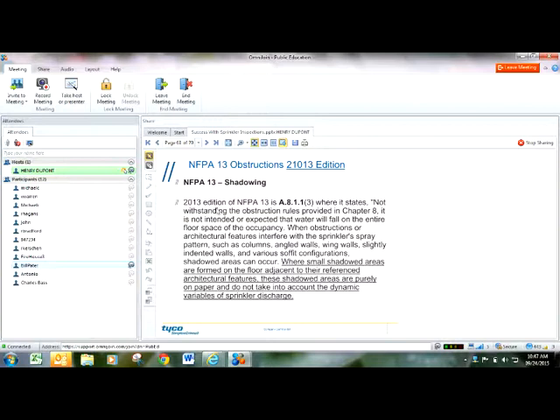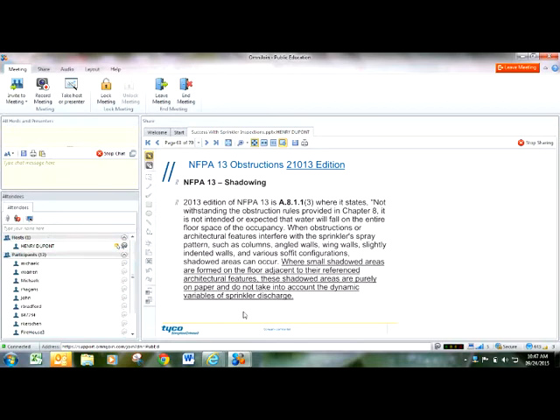Now, in regard to obstructions, the new 2013 edition of NFPA 13 did come out and say that some shadowing is okay. So in areas formed on the floor adjacent to their referenced architectural features, these shadow areas are purely on paper and do not take into account the dynamics of a sprinkler system. So if you're in a room and there's a beam that protrudes from the wall, maybe 12 or 14 inches, and you can tuck yourself up next to that beam and see that the sprinkler head wouldn't be able to spray water on you, that would be considered shadowing. It's not obstructions, it's just a shadow. The intent of sprinkler systems is to sprinkle the floor area, and the sprinkler head is going to do that regardless of whether there's a shadow or not.